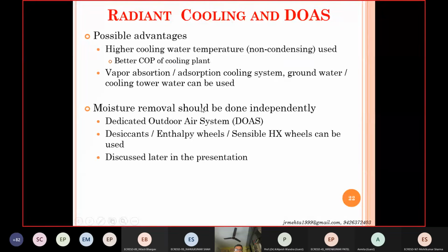Yes. So here moisture removal should be done independently using dedicated outdoor air systems, and in this system there would be options. One of the important parts of this is providing latent cooling or moisture removal from the outdoor air. So a desiccant system can be used for that purpose, and it also employs enthalpy wheels and sensible heat exchange wheels. Because of this, you are able to recover the cold. Otherwise, that would get exhausted, unutilized, to the atmosphere.